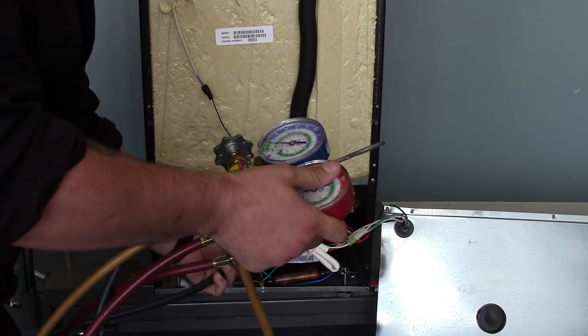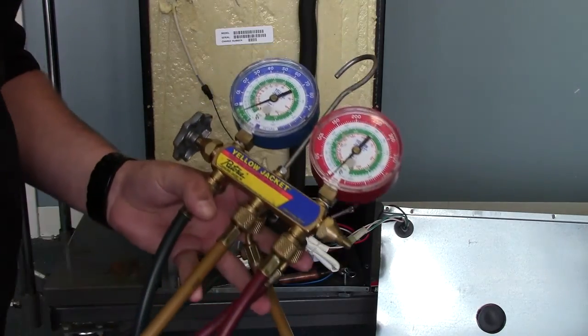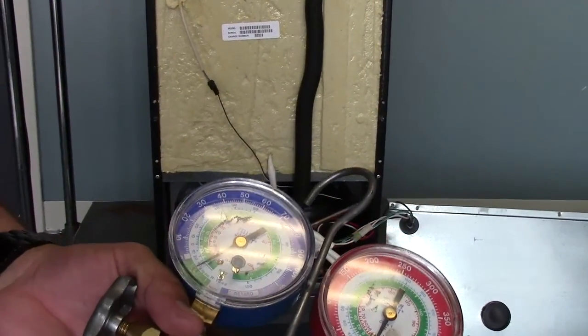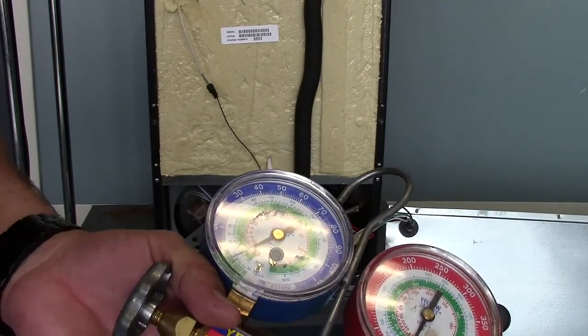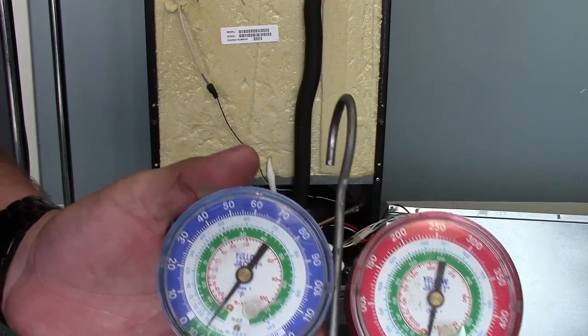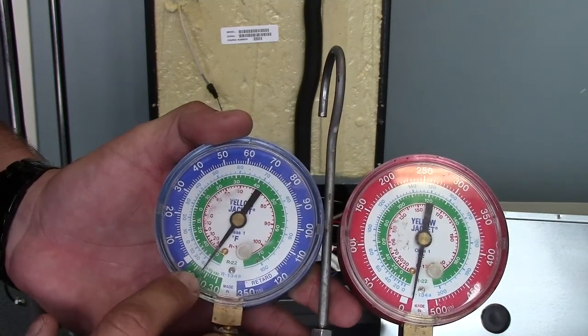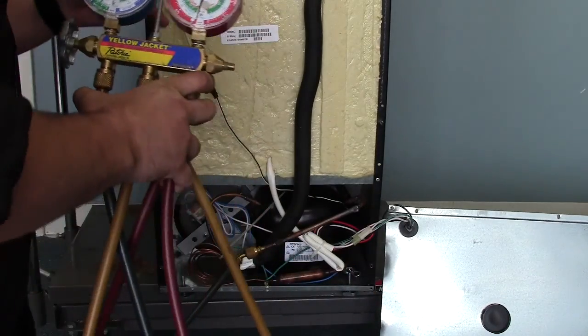Grab the low side of the gauge, and at this point I just plugged it in. I don't know if you can see that, but we're in a vacuum, about a 20 pound vacuum. So this system is completely out of Freon.